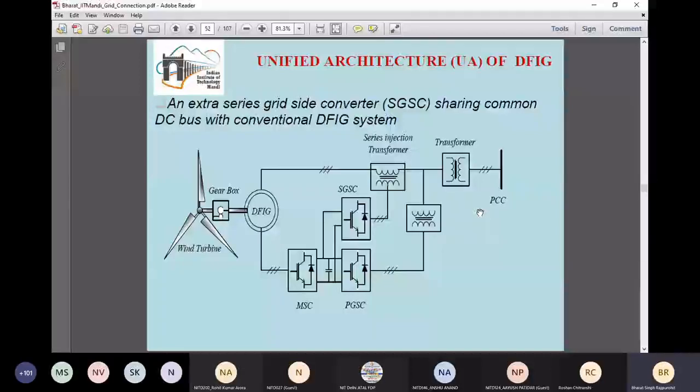Because some of the researchers have seen that during a fault condition, there are severe oscillations happening in the doubly fed induction generator due to poorly damped poles in the stator flux, and hence this compensation can be provided during the abnormal condition, acting as a series compensation to reduce the oscillations by adding some damping into the system and to have a well behaved system.